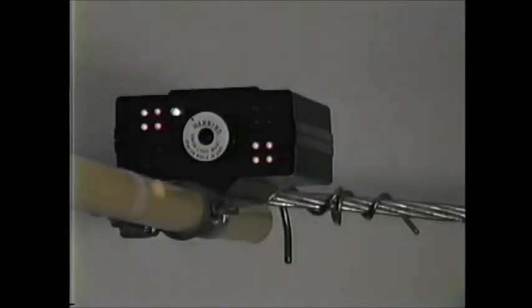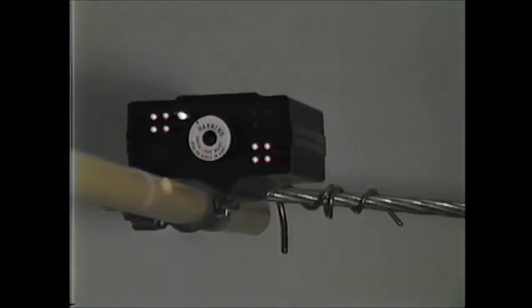We now have the HLS 5 hooked up on a line simulating a 13.8 KV line. Notice that we do get all three banks of lights flashing. We will now put a jumper around that and change the electric field to see what effect it has.